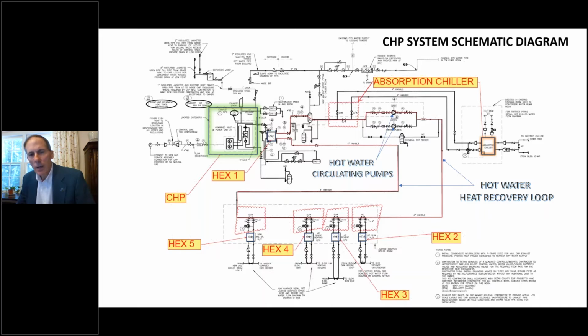The water circulates to heat exchanger number 2 first. If there's enough thermal load that the temperature of the hot water drops below 170 degrees, all the other heat exchangers are bypassed and the water flows back to heat exchanger number 1. If there's additional thermal content that can be utilized without the temperature dropping below 170, the water flows to the next heat exchanger, and so on until all the useful heat has been taken from the system without the temperature dropping below 170. The water circles back to heat exchanger number 1, is warmed back up, and loops around again. That's the general concept for how the thermal portion of the system works.